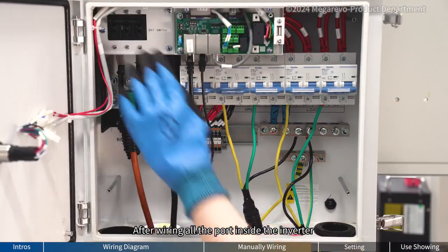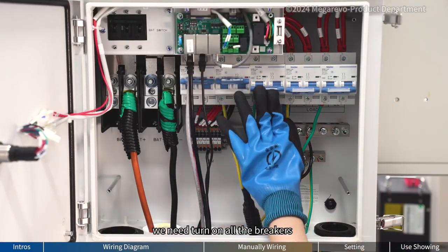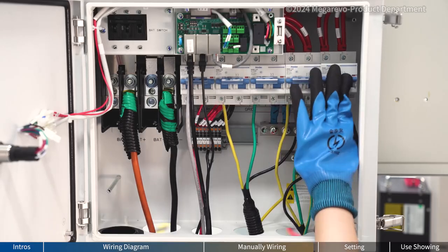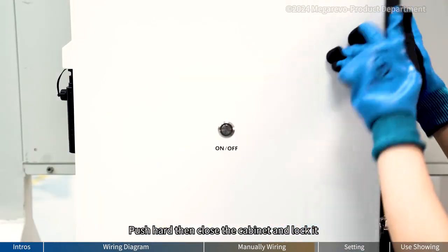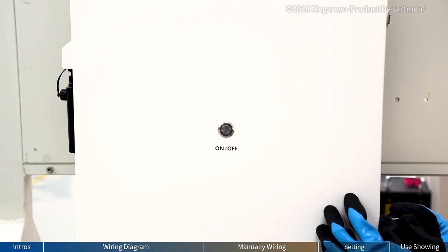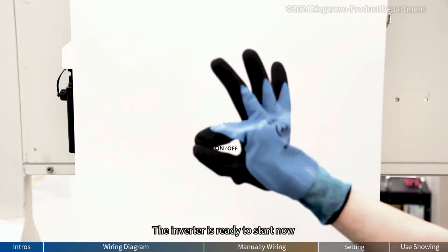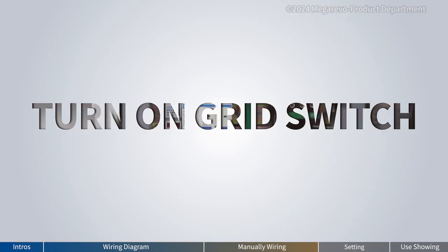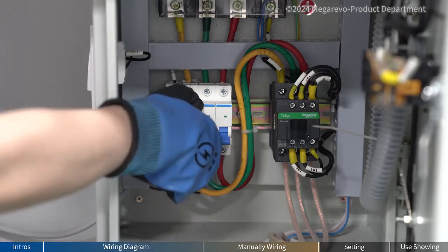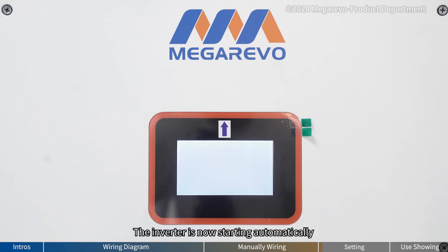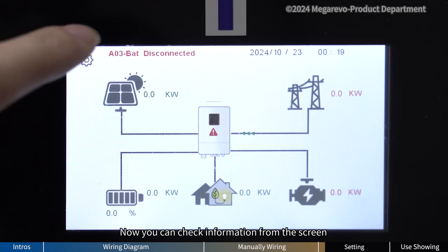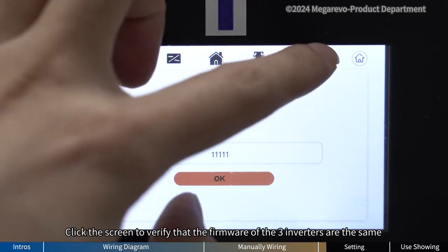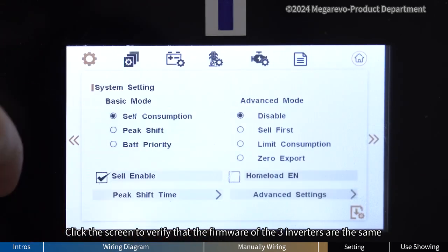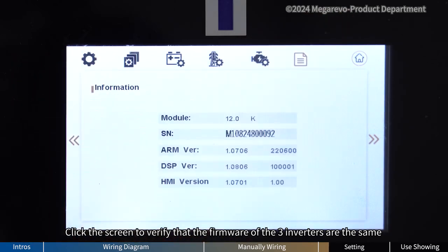After wiring all the ports inside the inverter, we need to turn on all the breakers. Push hard, then close the cabinet and lock it. The inverter is ready to start now. The inverter is now starting automatically. Now you can check information from the screen. Click the screen to verify that the firmware of the three inverters is the same.